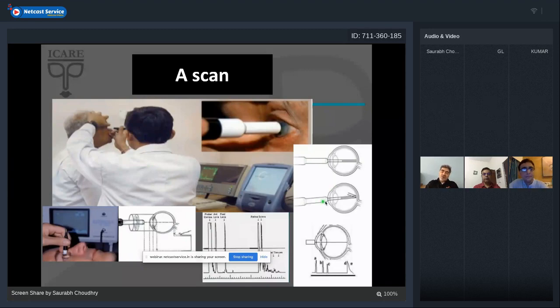What if the transducer is not placed well, it is placed at an angle, then you have the sound which is bouncing back at a different angle and your axial length will not be correct. So it is mandated that you need to look at these graphs once you are doing an A scan. All these graphs should end in a tip here and not flat like this. This is the first one which is at the cornea, which is flat, which is normal, but all these should be spiked like this, and some of them should be short like here where A, B, C is smaller and D is coming up.